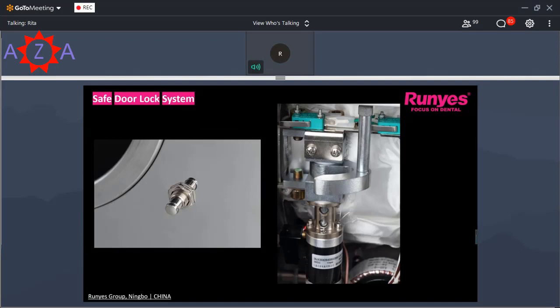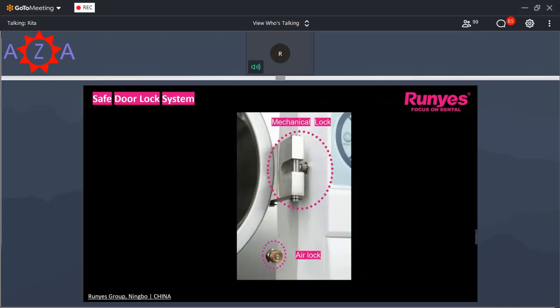All our autoclaves have a double lock system to ensure safety. So when the pressure and the temperature go up in the chamber, the airlock will automatically work to ensure safe use. This is the picture you see. This is the automatic door system with the touch screen. And this one is for the manual door system, mechanical door lock, and the airlock as well. So while the machine is working, the door cannot open to ensure safety. It's very important.